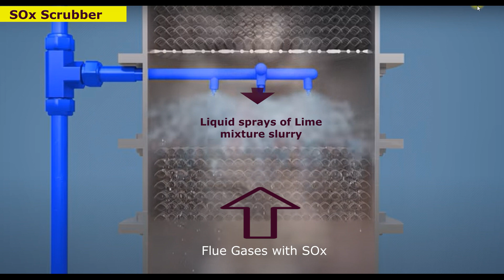Here flue gases enter from the bottom of a large duct which passes through a number of flow straighteners. See, a large number of flow straighteners are arranged across the duct to get uniform distribution of flue gases. At the top, there is a header of liquid. The liquid comprises a solution of limestone and water, and the alkali solution of lime and water is sprayed over the flue gases.